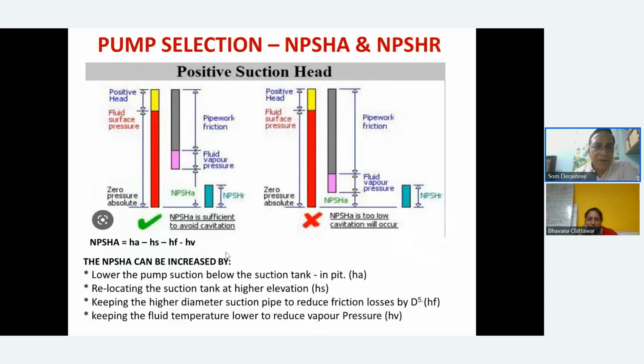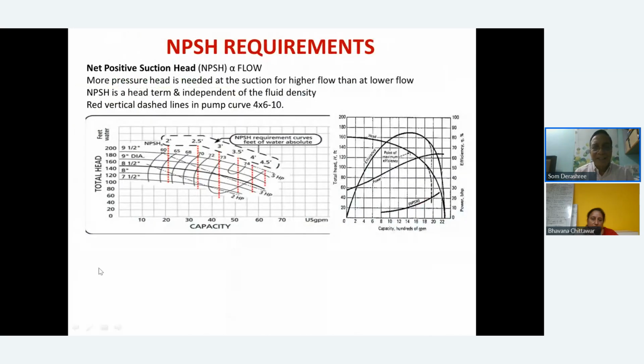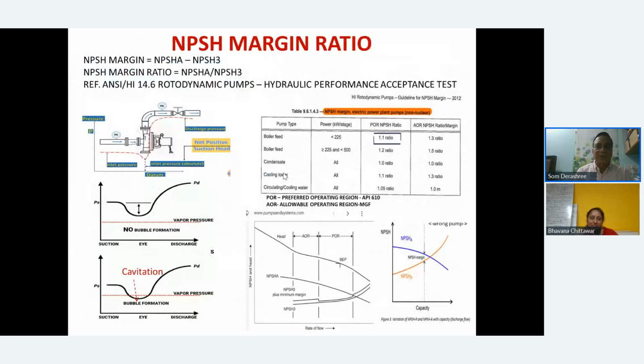Again, NPSH required is very, very important, because many times I have come across, even during audits, people who do not understand this and keep putting in a higher flow, higher capacity pump, thinking it is not pumping enough. If you put in a higher capacity pump, more cavitation will happen, because as the flow increases, the NPSH requirement also increases. The requirement goes up, but your friction and available head do not change, so with the increased flow, cavitation will start automatically. So that's not a solution.